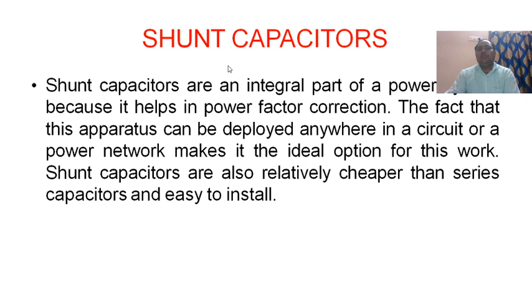If you observe the phasor diagrams without a shunt capacitor and with capacitors, this is without a shunt capacitor. There is only one impedance, R plus jXL. This is the sending end voltage, this is the receiving end voltage. Current travels from sending end to receiving end. If you take VR as a reference, current I is lagging, because all loads are inductive in nature. The IR drop is always in phase with current. I XL is 90 degrees from the resistive drop. The sum of VR plus IR plus I XL is the sending end voltage.